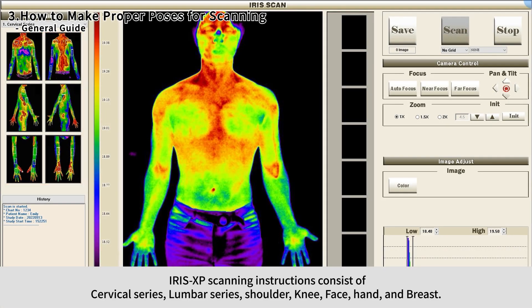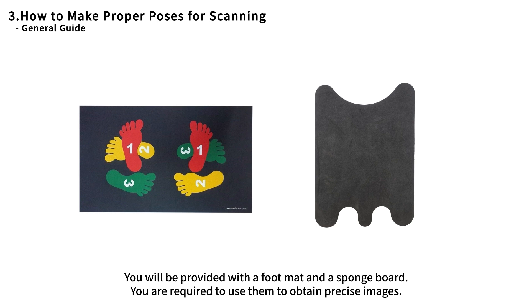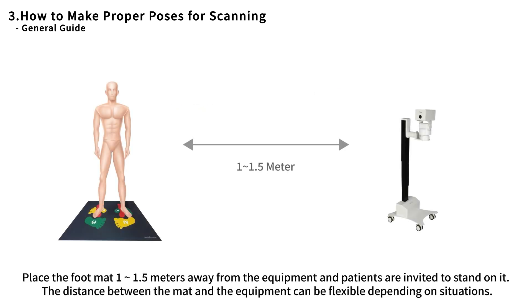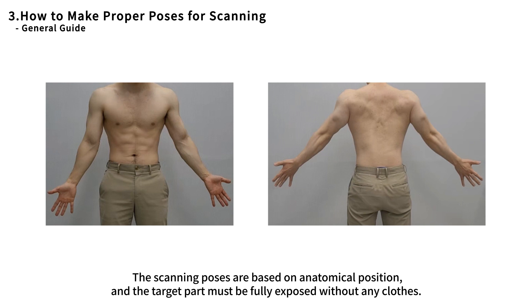Iris XP scanning instructions consist of cervical series, lumbar series, shoulder, knee, face, hand, and breast. Please refer to the guidelines on the left side of the screen. You will be provided with a foot mat and sponge board — use them to obtain precise images. Place the foot mat 1 to 1.5 meters away from the equipment and have patients stand on it. The distance can be flexible depending on the situation. Scanning poses are based on the anatomical position and the target part must be fully exposed without any clothes.